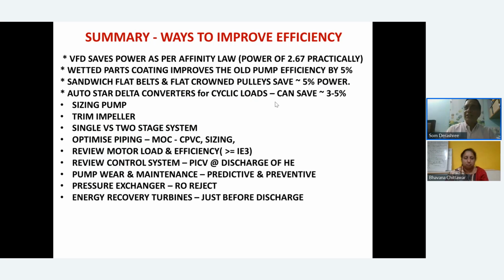So if you have a star delta starter already in place, it will sense the current from the CT, and if it is less than 50%, it will convert to star mode. Otherwise, it automatically goes to delta mode. Then pump sizing has to be proper, impeller trimming, single versus 2-stage system, and optimizing piping, that is the MOC. Even CPVC now has much less frictional losses and less corrosion. Use liberal sizing even at the design stage. Review motor load and efficiency, and go for more than IE3 right now.